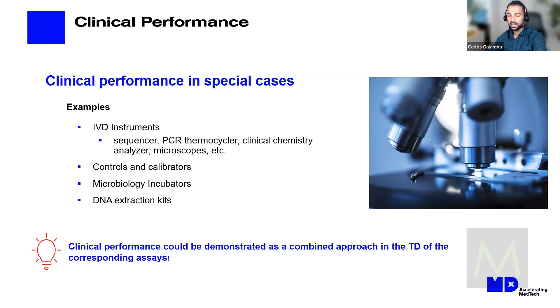Okay. So then what I wanted to talk about next is clinical performance in certain special cases. It's very similar to what I was saying. For example, in a lot of cases in the IVD world, you've got IVD instruments, which is the machine that runs your test, controls, calibrators, DNA extraction kits, and that sort of thing. And in a lot of these cases, I've seen manufacturers demonstrating clinical performance as a combined approach. So they typically focus on the assay. They don't say that clinical performance for my instrument is not applicable. They say it is applicable, but it's demonstrated via this assay, this test, and here's the documentation to support it. So in a lot of cases, clinical performance can actually be demonstrated as a combined approach based on certain devices. The examples are controls, calibrators, IVD instruments, incubators, and those sorts of IVDs.